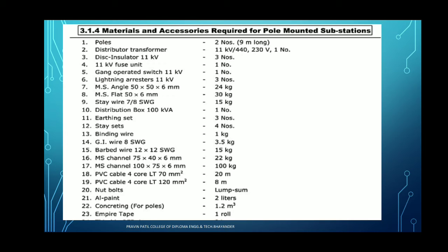Then PVC cable of 4 core LT 70 mm square, 20 meters of the cable is required. Then PVC cable of the same type is also required for 8 meters. Nuts and bolts are also required, a lump sum for fitting purposes. Then Al-paint, 2 liters of Al-paint may be required. Then concrete for the pole, 1.2 cubic meters. Then insulation tapes are required, 1 roll. So these are the materials and accessories required for the pole mounted substation.